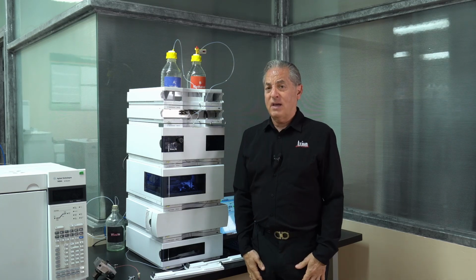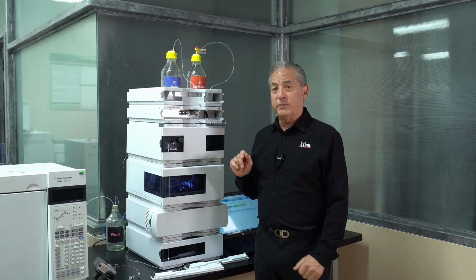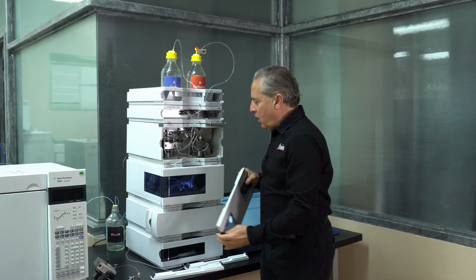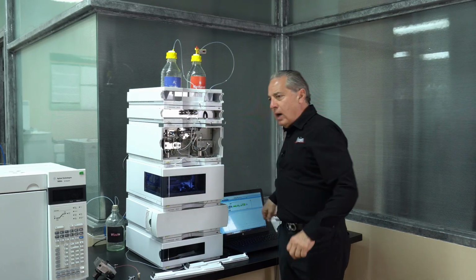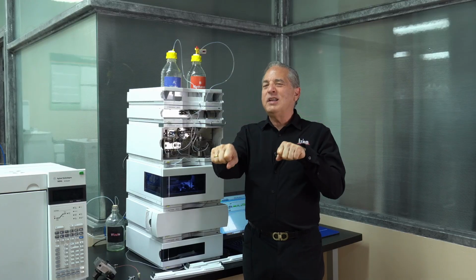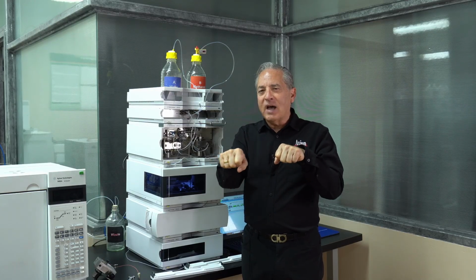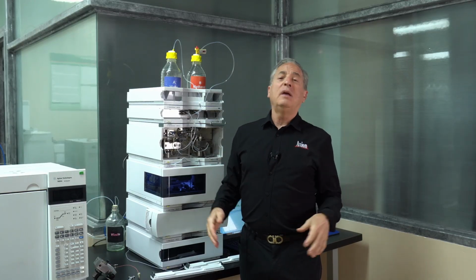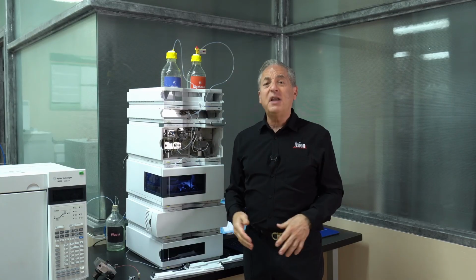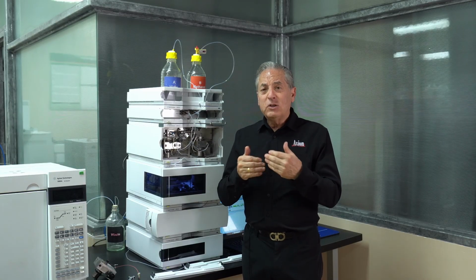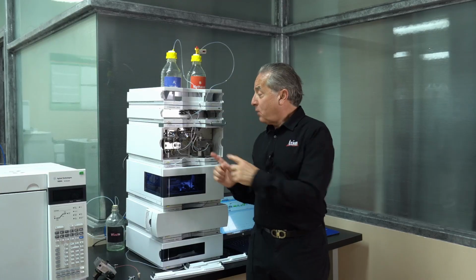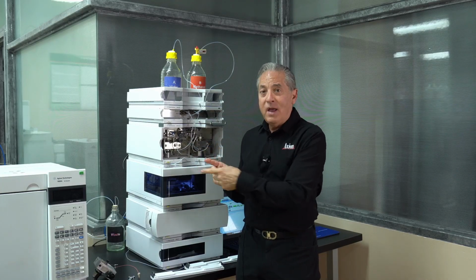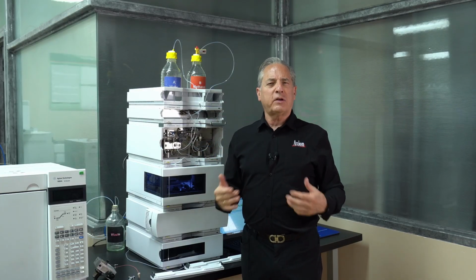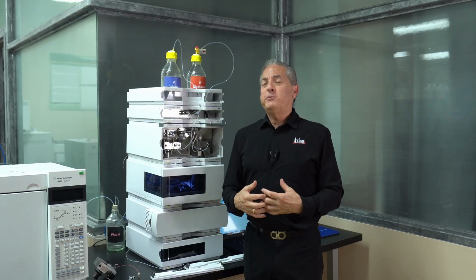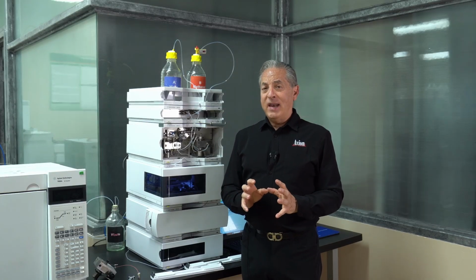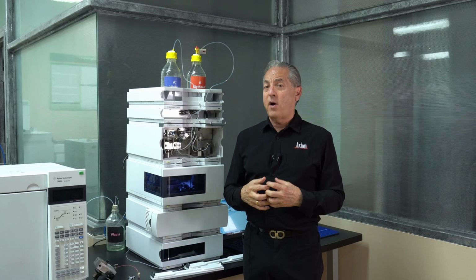The major maintenance item in your HPLC is going to be your HPLC pump. The pump is doing all the work, right? It is moving back and forth. It is producing extremely high pressures of 9,000 psi. It has to produce a flow rate precision within 1% RSD, and much less than that. So it's got to produce the right flow. It's got to produce the right blend of methanol and water, because any one of those problems is going to affect our chromatography. So the pump is really well designed. And it's the thing that eventually is going to require maintenance.